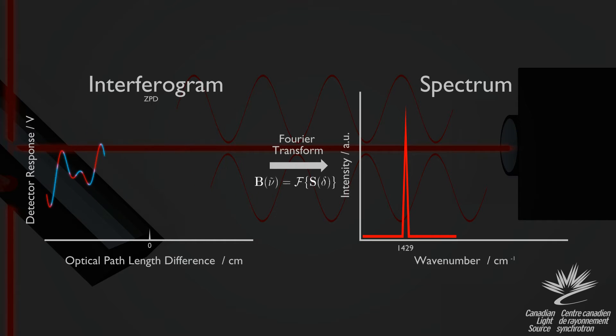Suppose we mix in a second color of light with the first. Now the interferogram is the sum of the two sine waves. Each component moves in and out of phase at a rate unique to that wavelength of light, as the mirror must move a different distance to cancel out light of a different wavelength. Taking the Fourier transform again, we observe another spike in addition to the first, located at the new wave number. This tells us that the interferogram is made from two discrete wavelengths.